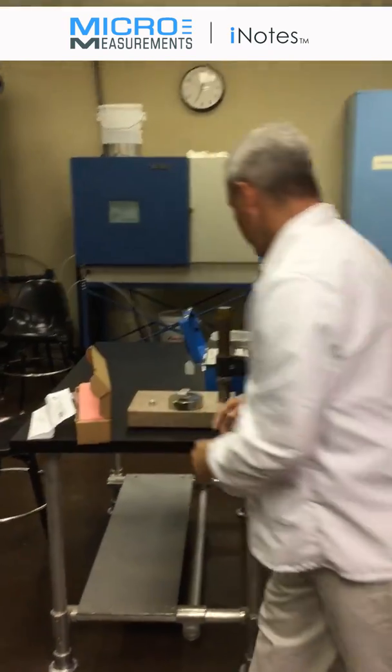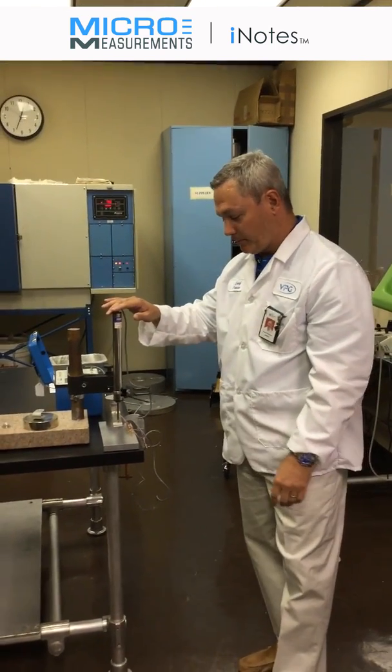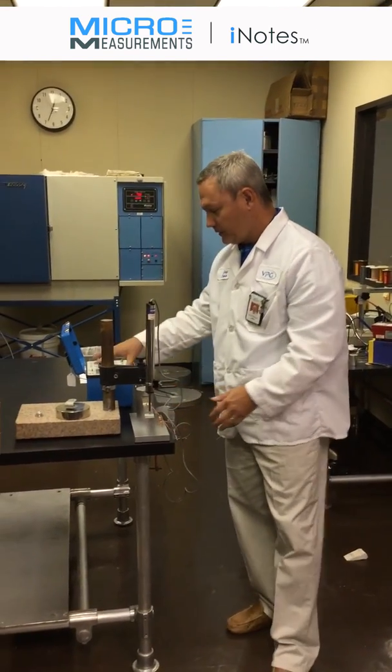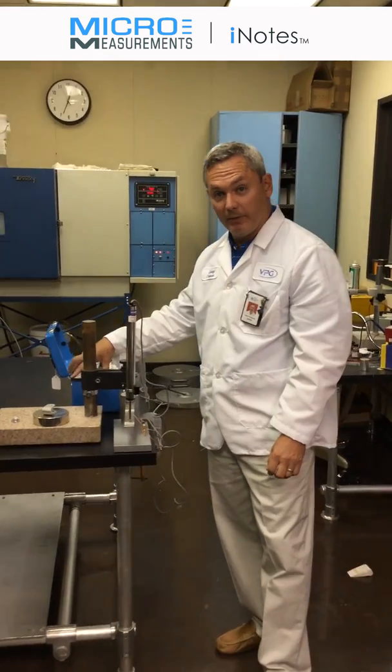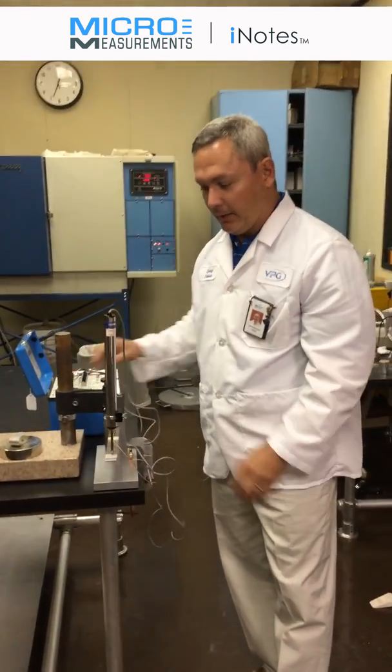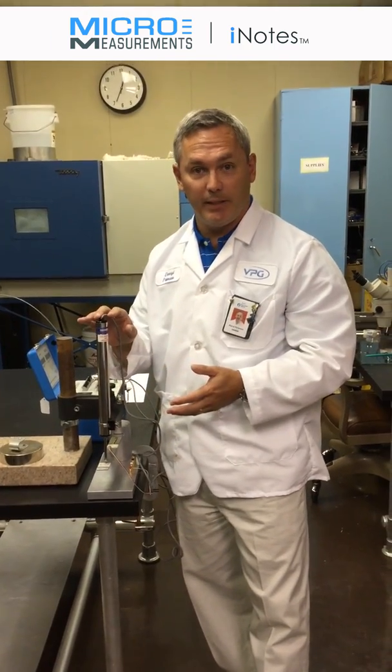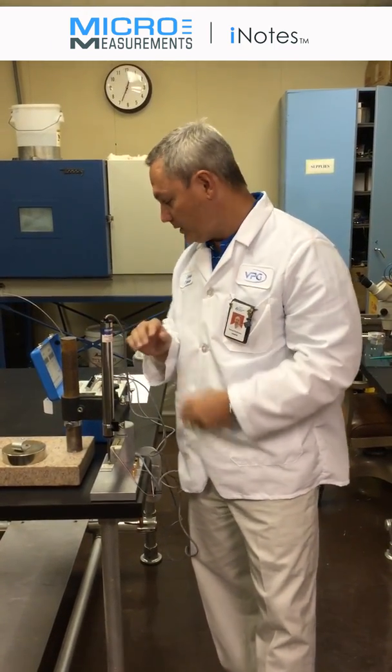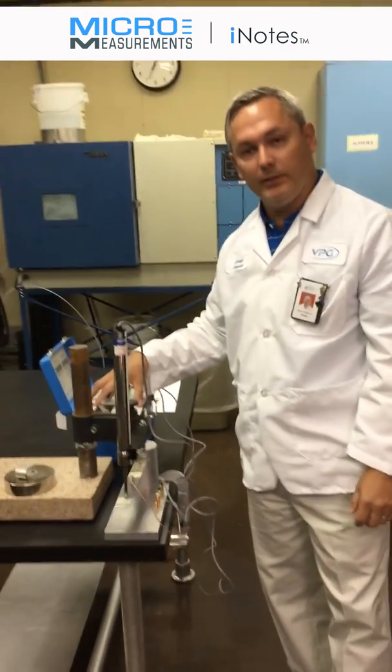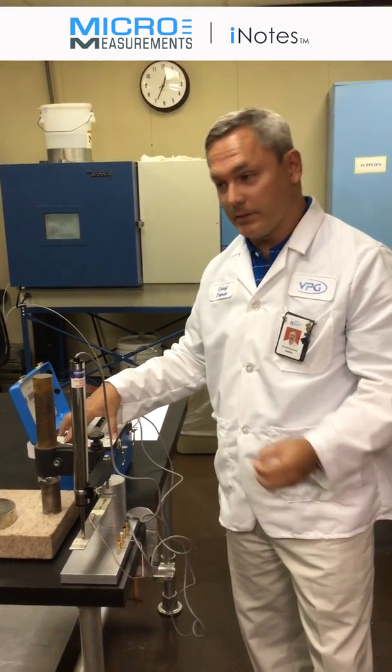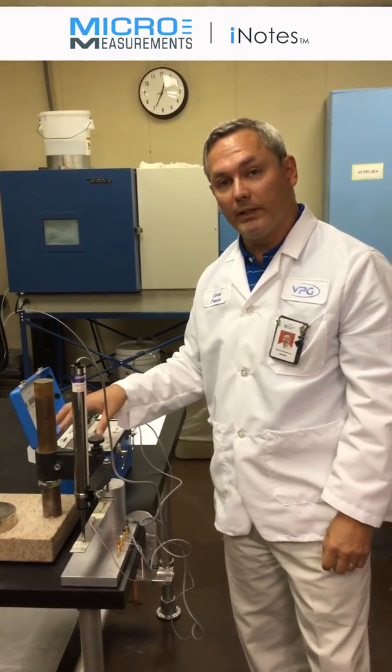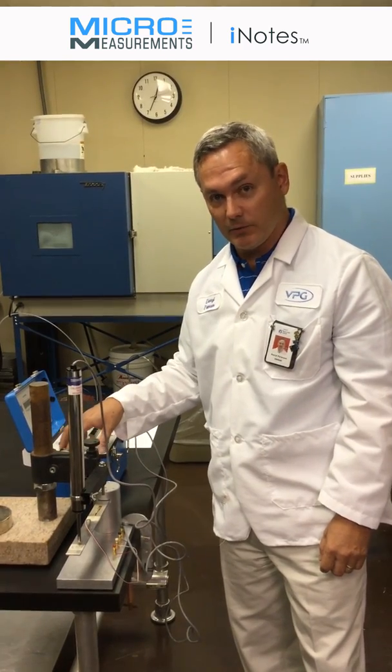Now, I've also got set up one of our HS100s. It's connected into this blue box, which is a model P3 strain indicator recorder. One of the advantages to using these types of sensors is that they're strain gauge based, so you can connect them into any strain gauge instrumentation, whether it's a strain indicator, signal conditioning amplifier, or data acquisition system that's set up for gauges.